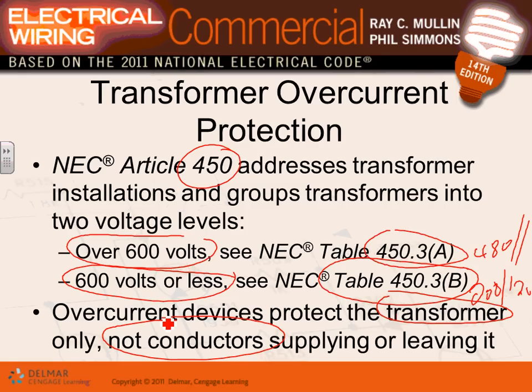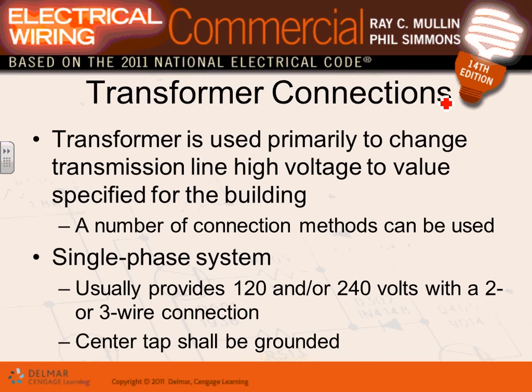So that's why when we do transformers, guys, you have to pay attention that there are conductors to be protected, and you have to pay attention to the tap rules. I go through the tap rules, guys, for conductors in the industrial project. So when we have a transformer right here, and you put a fuse on this side, and a transformer, a fuse, and a disconnect on this side, of course, these fuses are meant to protect the transformer, not the conductors. They will be protecting the conductor when you arrange it based on the tap rules, which again, we will do in the spring.